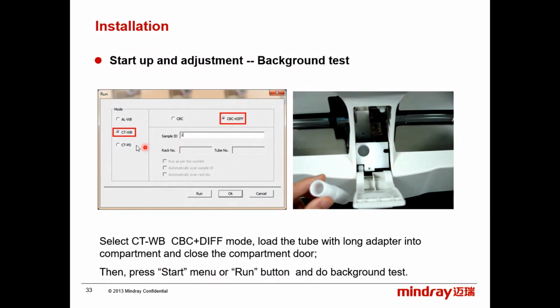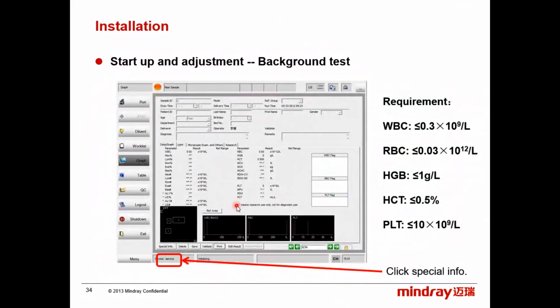Now, the background test. Okay, select closed tube whole blood, CBC plus diff. Load a tube with long adapter into the compartment and close. Okay, here it will just do some air aspiration. All right, and this is the requirement for the background test. All right, when we reach the fluidic, or maybe the last session, we'll focus more on troubleshooting this background or samples and so on. Okay, if you have, for example, high platelets, what is the cause? Hemoglobin not good, and so on.